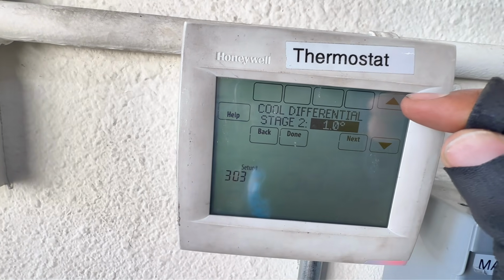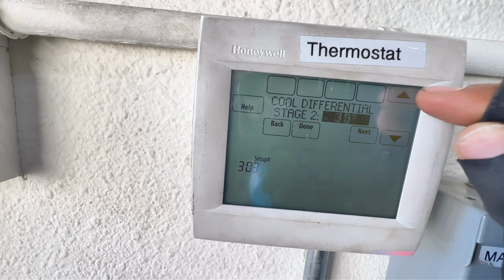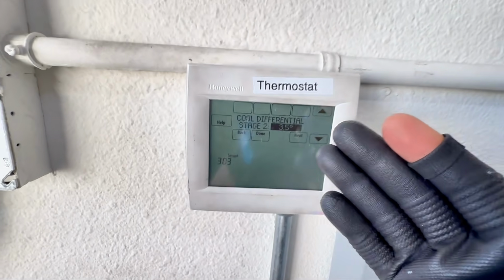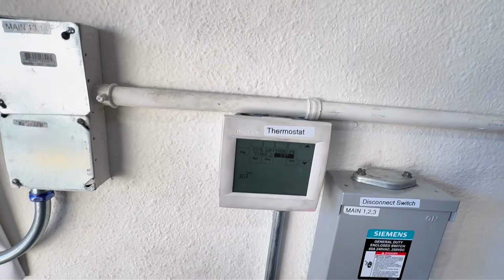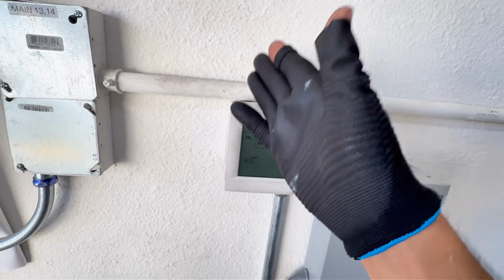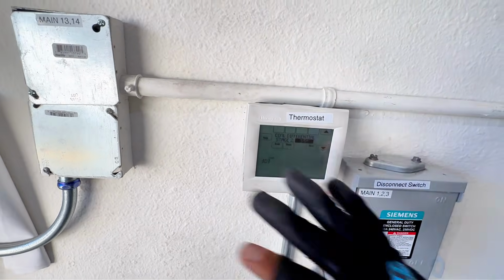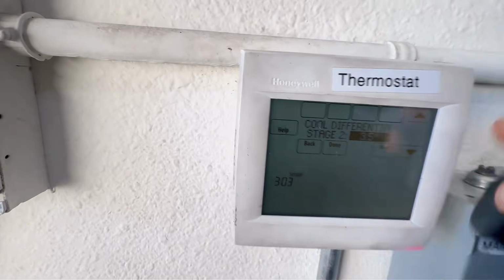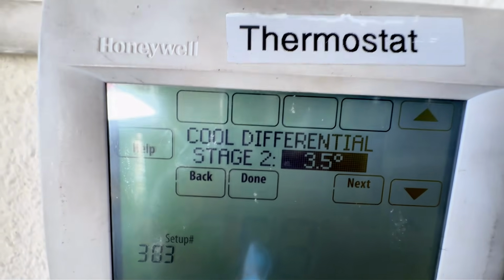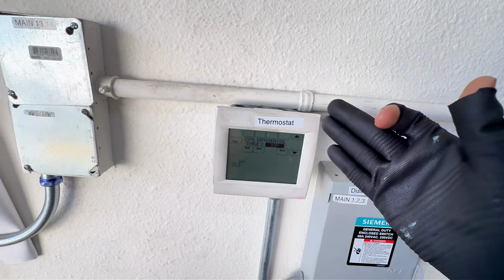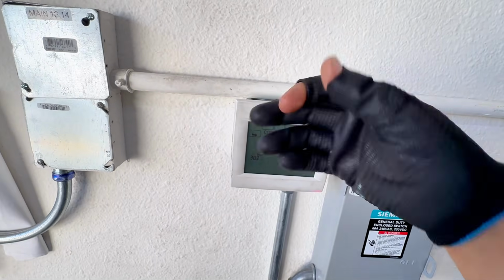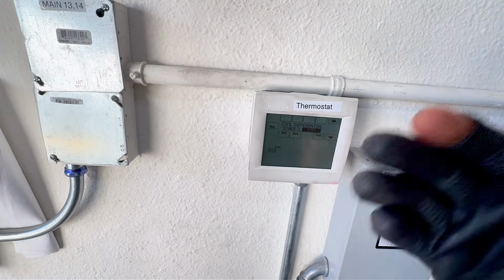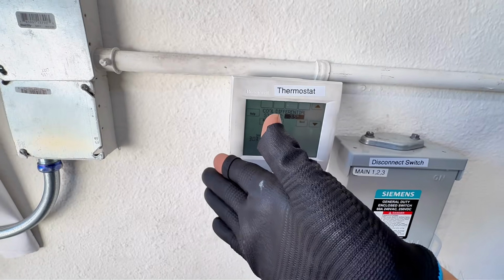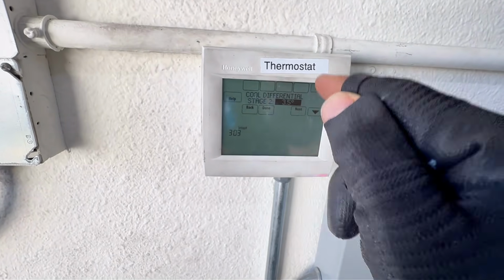You've got comfort, then 1 degree, 1.5, 2, 2.5, 3, 3.5. That's the greatest. So it's simple. If you have a set point of 70 degrees, and the ambient temperature in your house is 72, and let's say we choose 3.5 degrees, that means the difference between the ambient temperature and the set point has to be greater than 3.5 to do stage 2. So if you put a set point of 70 and your ambient temperature is 72, it's only going to do stage 1 because it's not greater than the 3.5 degrees.